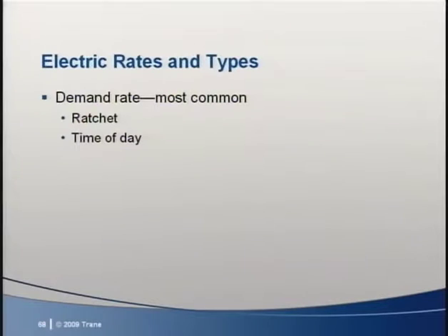The first rate to look at is the most common, a simple demand rate. They tend to vary. Some might have a time of day energy price, but most don't. A common myth about ICE energy storage is that time of day rates with low nighttime kilowatt hour charges are needed to make the economics work. That's not the case. Most of the ICE storage projects do not have time of day rates.